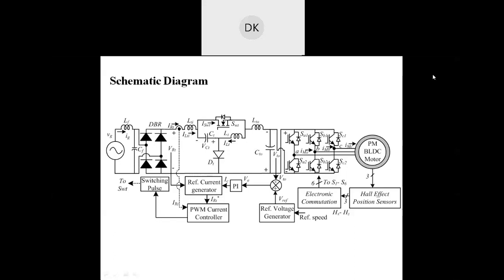Sensors have their own sampling time requirements, like the Hall effect sensor. If you are measuring voltage and current, you usually go for Hall effect voltage sensors and current sensors. Hall effect current sensors require very little time, usually less than 1 microsecond. But voltage sensors require a larger time for sampling, usually 20, 30, or 40 microseconds, and sometimes even 100 microseconds, depending on the quality of that particular sensor.